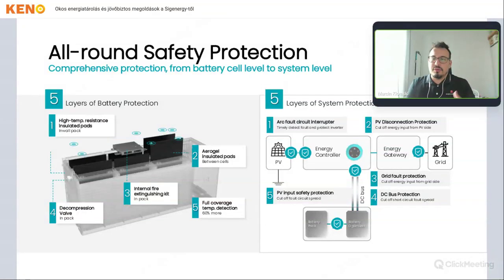In our definition, we define the storage as a crucial element for the market where there is high demand, and we have to allow customers to put it inside buildings. So we redefined the level of the safety systems. What our HQ thought from the very beginning was to split the container solution into individual elements and implement safety per element, ensuring fire and temperature will not go outside the closed protection of the battery.